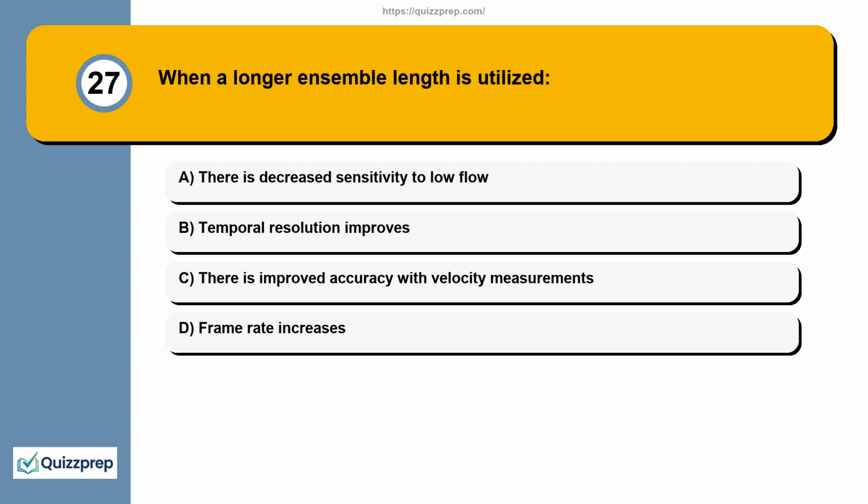Question 27. When a longer ensemble length is utilized, there is decreased sensitivity to low flow. Temporal resolution improves. There is improved accuracy with velocity measurements. Frame rate increases.